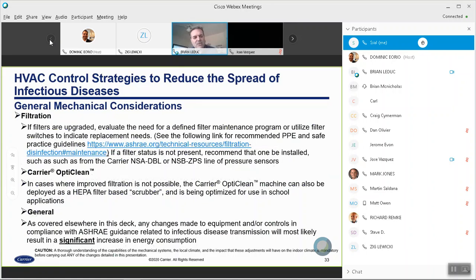The OptiClean, which hopefully you know a little bit about from the marketing releases, originally was deployed to create negative pressure zones. What was shared with me yesterday is that they're actually looking to optimize it for use as an air scrubber with HEPA filters, and the application that I saw was installing one or more OptiCleans in a classroom. Basically it's just to recirculate and clean the air that's in the room.